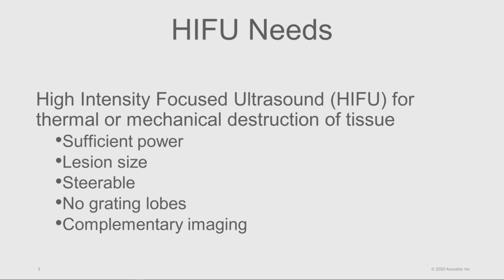The most common choices are magnetic resonance imaging, which is the gold standard for 3D imaging in HIFU, however requires an MR-compatible transducer and a large, expensive MR system. Ultrasound imaging with additional transducers is simpler and lower cost, however rarely offers 3D volumes to improve targeting.